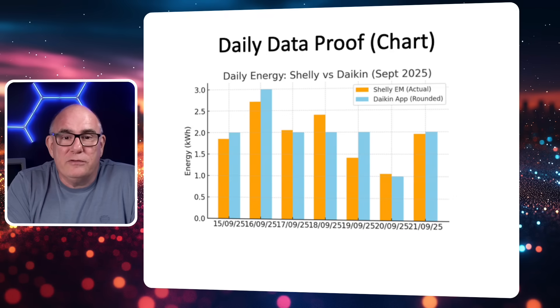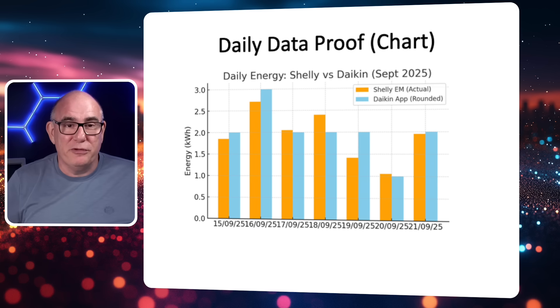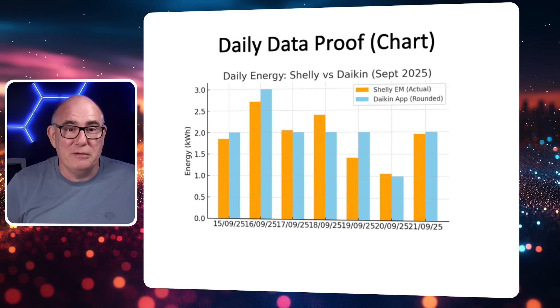Both AI systems confirmed that Daikin rounds daily data to whole kilowatt hours, but it doesn't do this consistently. For example, on the 18th the Shelly was reporting about 2.3 kWh and the Daikin reported 2 — so it rounded down, which seems reasonable. But on the 19th the Shelly was reporting about 1.4 kWh and Daikin rounded up to 2. It's not following standard rounding rules — it's doing things at random. On days with really low usage, maybe 1 to 2 kilowatt hours as we've seen on summer days when we're just heating hot water, the rounding error can introduce as much as 30 to 100 percent uplift in the number.